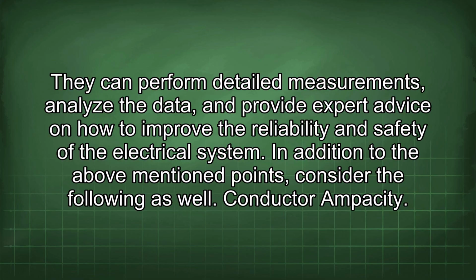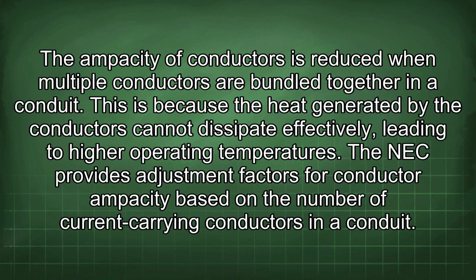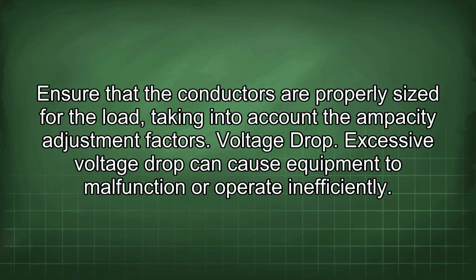In addition to the above-mentioned points, consider the following as well. Conductor ampacity. The ampacity of conductors is reduced when multiple conductors are bundled together in a conduit. This is because the heat generated by the conductors cannot dissipate effectively, leading to higher operating temperatures. The NEC provides adjustment factors for conductor ampacity based on the number of current-carrying conductors in a conduit. Ensure that the conductors are properly sized for the load, taking into account the ampacity adjustment factors.